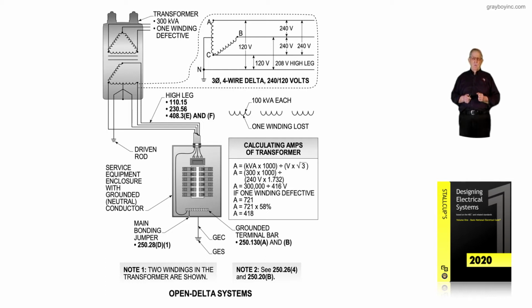What are the other advantages of an open delta system? Well, let's review the calculating amps of the transformer, that boxed in information. Now notice each transformer is 100 kVA each. And right above the calculating amps of the transformer, we have lost one of those windings. So we're going to reconnect it delta as you see in the illustration, but it's going to be open delta, not closed. Then notice when we did the calculations, we come up with 721 amps as you see in the illustration, just like we calculated previously.